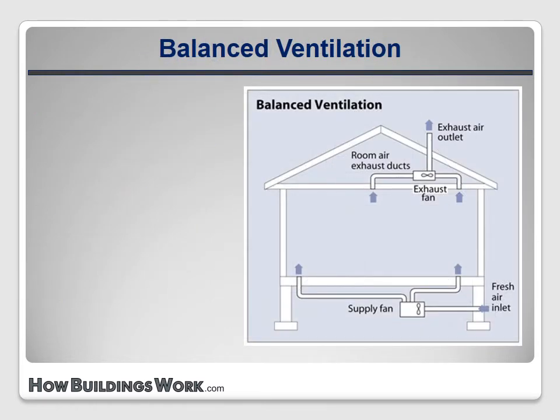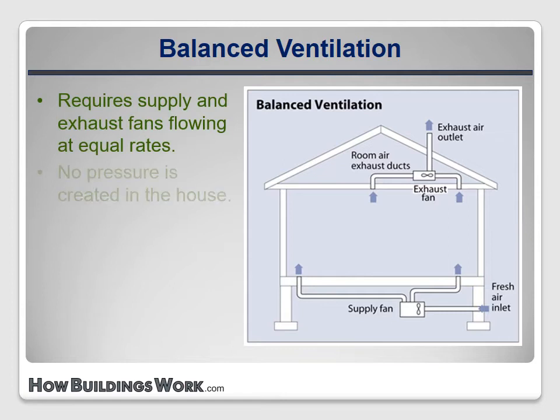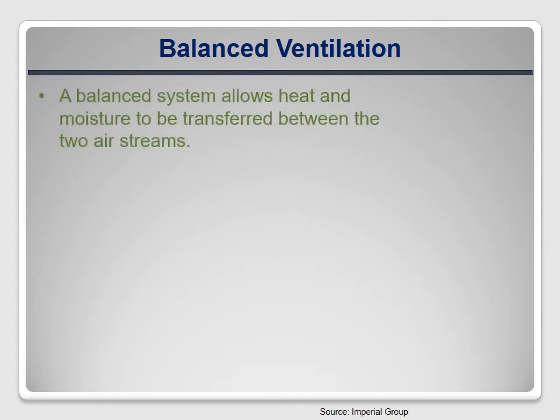Balanced ventilation is the third possible strategy. As you can see from the diagram, two fans are present — one draws stale air out of the house and the other pushes fresh air in. Since the two fans have matching flow rates, no pressure is created in the house. If the supply and exhaust are at opposite ends of the house, the fresh air distribution should be fairly uniform. A balanced system provides the possibility of exchanging heat and moisture between the incoming and outgoing air streams. This can be very beneficial because it saves energy and it tempers the incoming fresh air, making the system more comfortable.